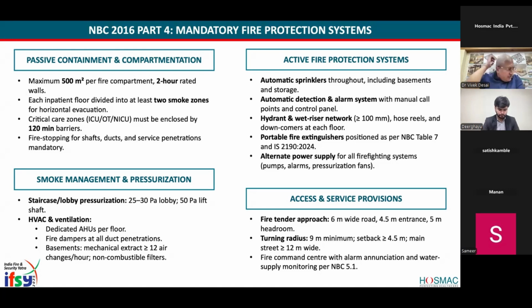So this is another important design criterion for planning hospitals. The fire tender approach: 6 meter wide road, 4.5 meter entrance, 5 meter headroom. This is the minimum required. It also needs a turning radius of 9 meters, minimum. So this is something where we go wrong. We do a 6 meter road all around the building, but we forget that it needs 9 meters to turn at the corner. So that needs to be planned properly. Otherwise, the fire engine will find it very difficult to go around. Okay. So this is something that one needs to keep in mind.